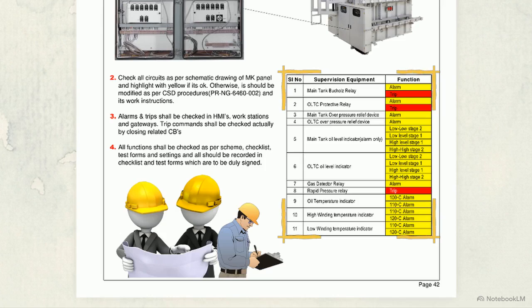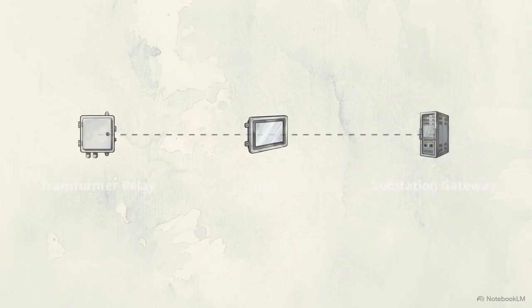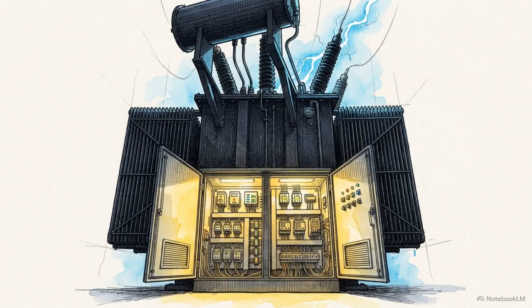Technicians manually actuate the Buchholz relay, pressure relief devices, and oil level floats to ensure each contact matches the designated function matrix. We follow the signal path all the way to the control room, verifying the trip commands through the human-machine interface to guarantee correct mapping to the substation gateway. These functional checks provide the final layer of assurance, proving the transformer's heavy copper and steel structures are actively guarded by highly responsive protection systems.